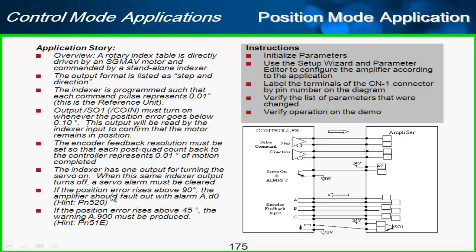And the last two here says if the position error rises above 90 degrees, if we get 90 degrees behind in the amplifier, we want to have the amplifier fault out, position error overflow. And also we would like to have a warning when we get halfway there, 45 degrees.